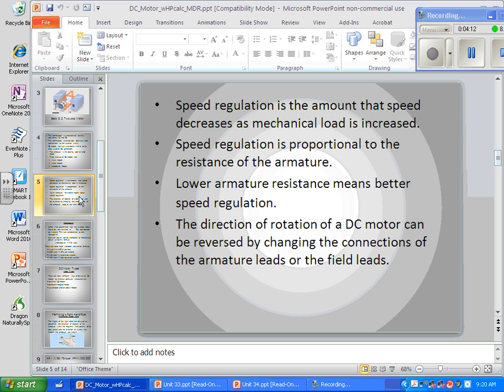At some point this semester, a student will tell me — with their drawing and their words — that they're reversing the armature, but the motor will run at a noticeably different speed. I'll say no, you've got the field winding being reversed instead. And they'll ask how I know. I'll say, look at the speed it turns forward versus in reverse — it will be obvious.